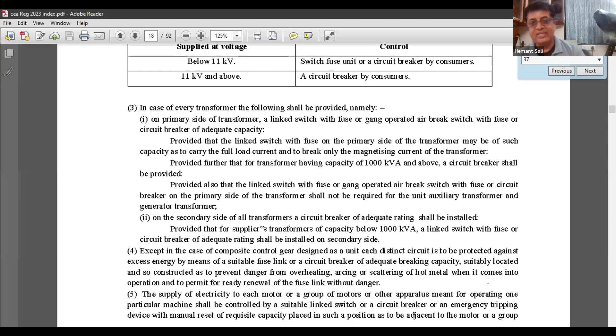Actually, from the point of view of safety, we cannot say that a 5 kVA generator cannot impose any life risk to any person, but still there is such a provision, maybe to reduce the number of inspections because of time delay, and because depending on the capacity of the genset, they might feel that smaller generators are not much of a risk. But it comes under the power of the government to decide which generators have to be inspected. Like Maharashtra, they have set a limit: 250 kVA generators and above have to be inspected by the electrical inspector. But of course, it is not that the remaining generators are not required to be inspected. That comes under the purview of the chartered electrical safety engineer or your regular inspection.